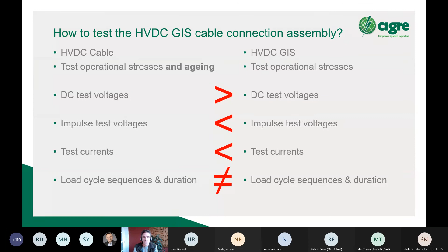Because if that is the case, then we can simply test the cable connection assembly as part of the HVDC cable PQ and type test, and we do not have to repeat any additional tests for this type of component. So that is the goal of this joint working group, to develop these dielectric testing guidelines for HVDC GIS cable connection assemblies by comparing the simulated internal stresses caused by the HVDC GIS testing requirements and the HVDC cable testing requirements to determine which is the most severe case.